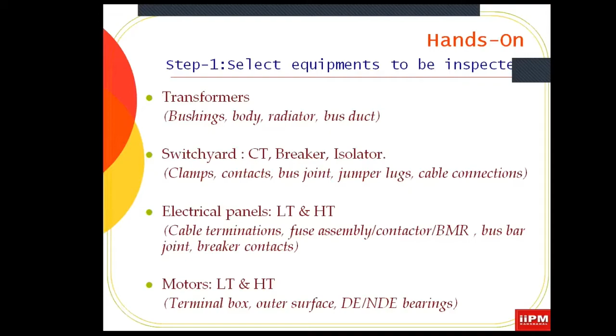First is to select the equipment to be inspected. Which equipment? Electrical, mechanical, electronics, panel, motor, transformer, switchyard, pipeline, furnace, buildings. Which equipment you want to inspect or take the thermography picture of, accordingly you have to set all these things in the camera. Then, before reading the manual instruction book, how can we set it? First, check whether the battery is charged or not.